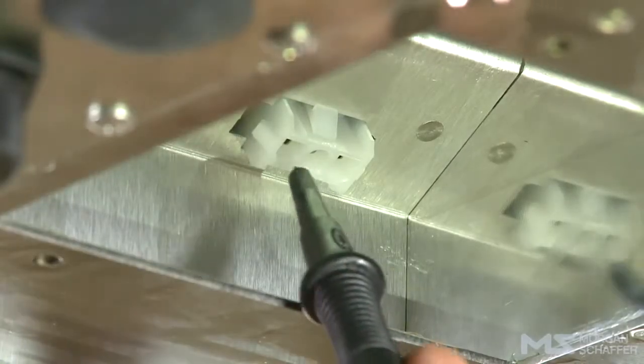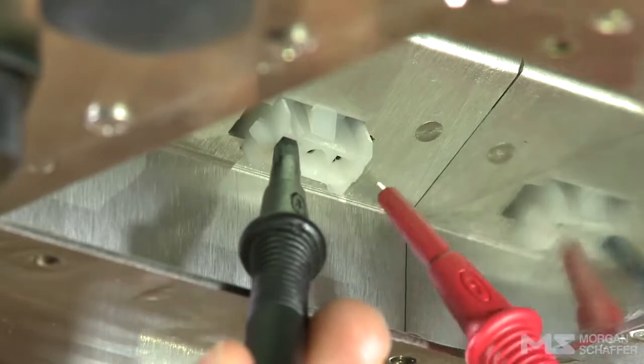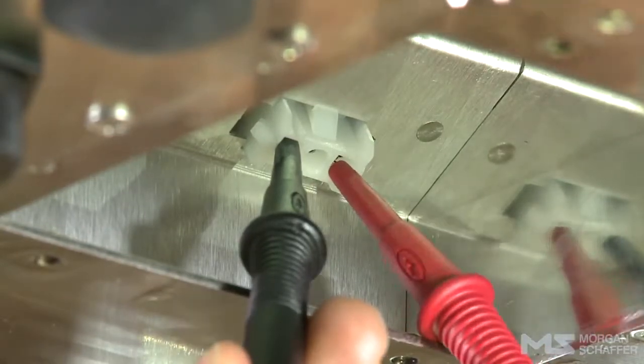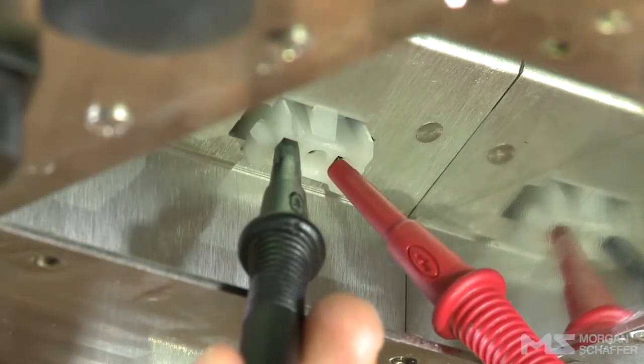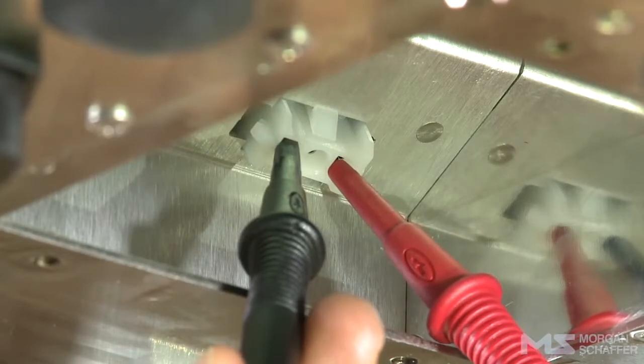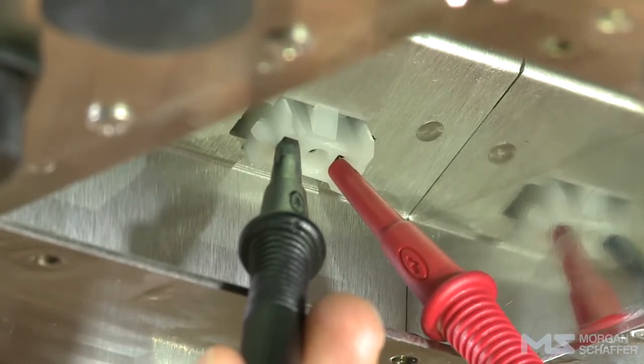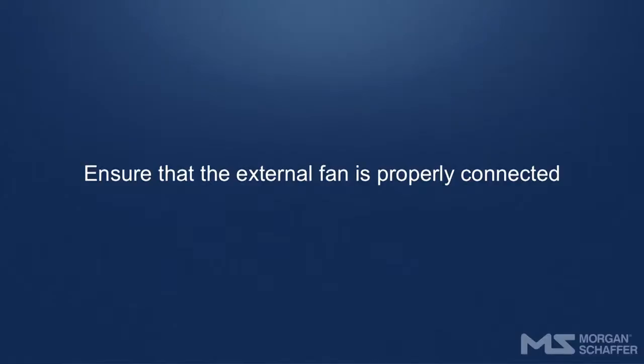Unplug the fan and using a multimeter, check that there are 13.5 volts direct current between pins 1 and 3 of the Calisto's female connector. If there are not between 13 and 13.5 volts direct current between pins 1 and 3 of the connector, please contact Morgan Schaffer.